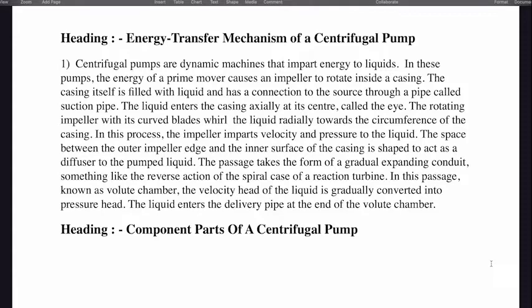In this process, the impeller imparts velocity and pressure to the liquid. The space between the outer impeller edge and the inner surface of the casing is shaped to act as a diffuser to the pumped liquid. The passage takes the form of a gradually expanding conduit, something like the reverse action of the spiral case of a reaction turbine. In this passage, known as the volute chamber, the velocity head of the liquid is gradually converted into pressure head. The liquid enters the delivery pipe at the end of the volute chamber.